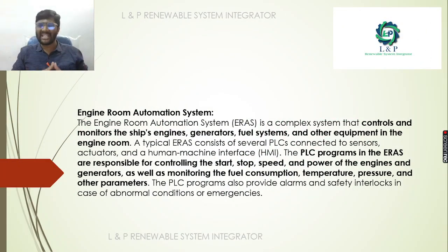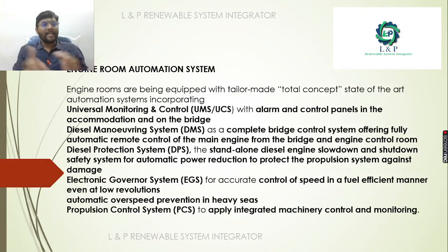It is a complex system which controls and monitors the ship's engine, generators, fuel system, and other equipment inside the engine room. For example, the PLC program in the engine room automation system is responsible for controlling the start, stop, speed control, and power control of the engines and generators, as well as monitoring the fuel consumption, temperature, pressure, and other parameters. The engine room control system is equipped with a tailor-made total concept. We have many categories in the automation system. One is universal monitoring and control with alarms and control panels in the accommodation and on the bridge.